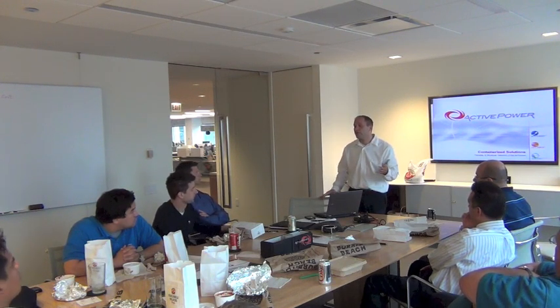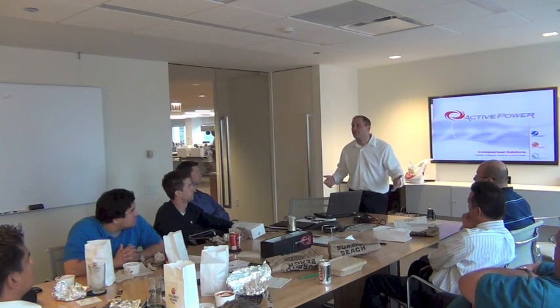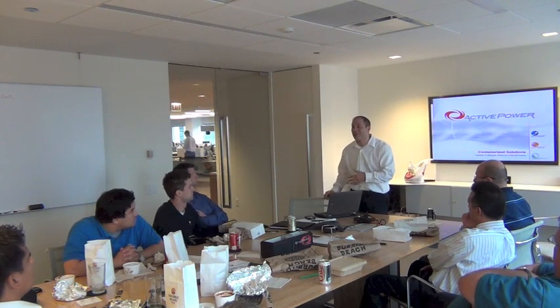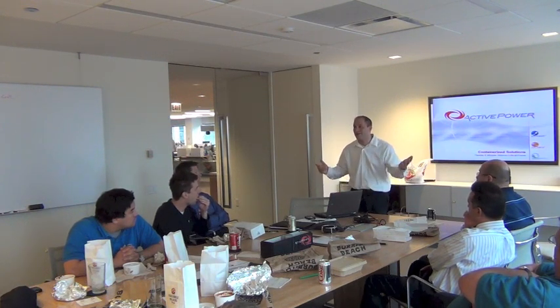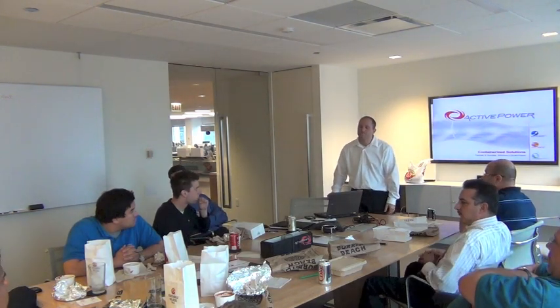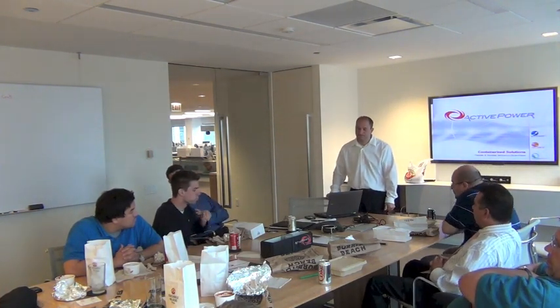But when you transfer to generator, you're going to be on generator for at least 3 or 4 minutes. So hopefully you're not transferring back immediately to utility. Hopefully there's a delay to let your flywheels recharge. That's up to the engineer to make sure we don't ever get into that situation.